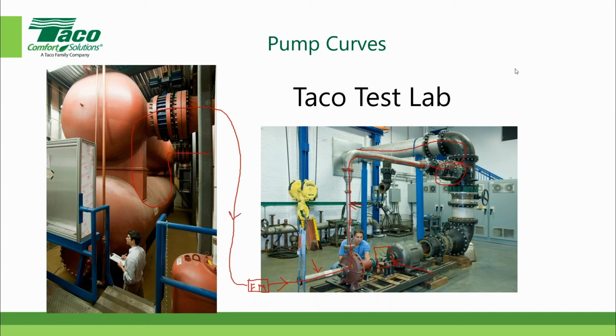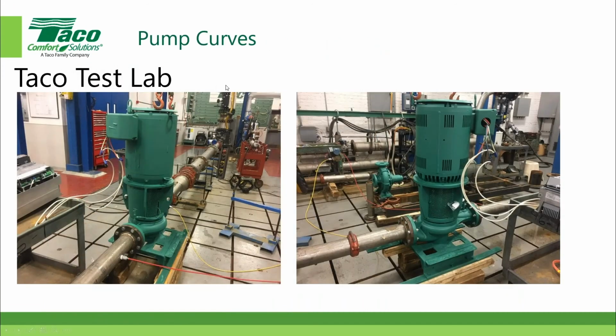So I got a couple of other photographs to make it a little easier to understand. So here is another pump that's being tested. This one is not being tested for performance. It's being tested to certify. This is called a certification test as opposed to a performance test. And the reason I know that is because we don't have the torque cell between the electric motor and the pump. So this is really being certified for a customer.